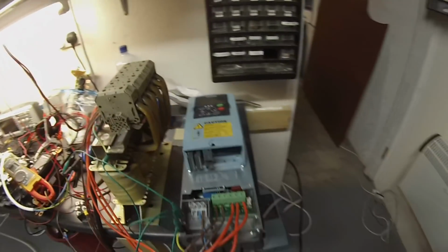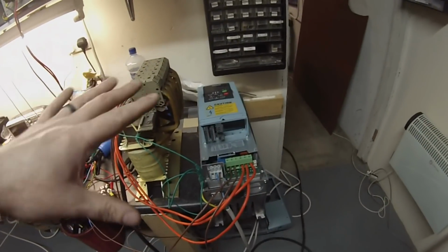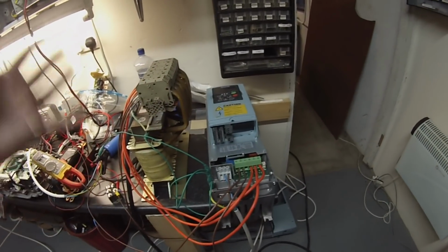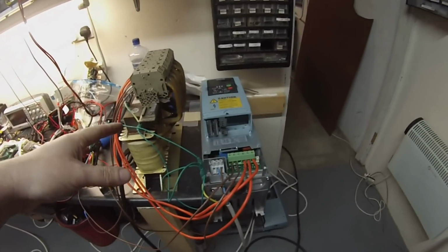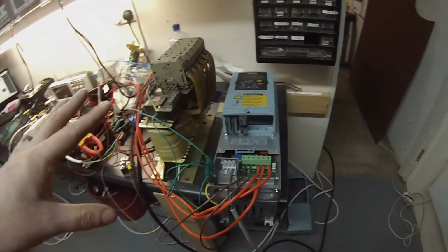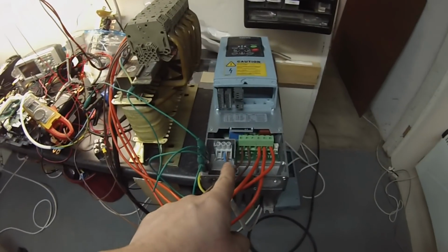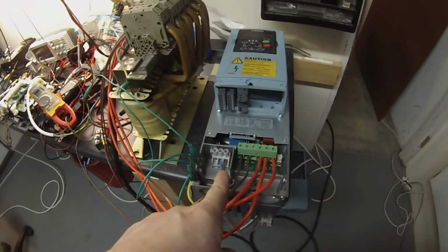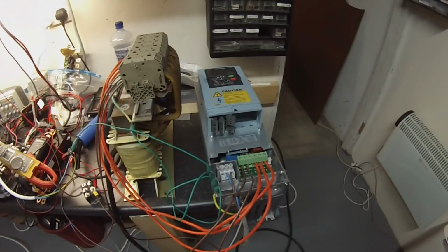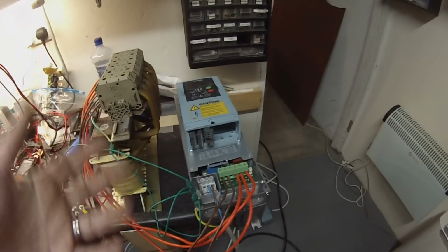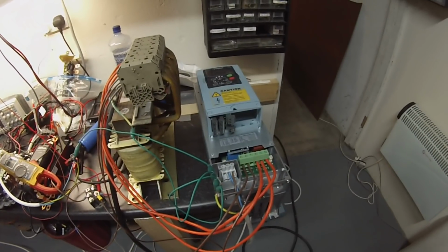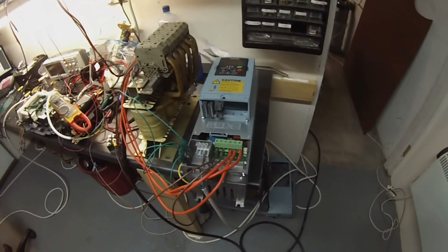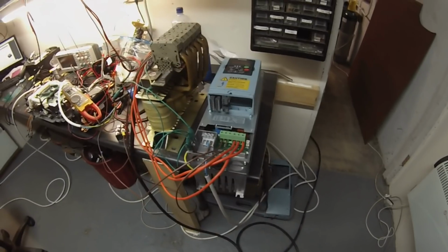So basically, what the Dino Guy showed was that you step up your 230 volt single phase to 400 volt single phase, feed that into your inverter, turn off the phase failure detection, set it to run 50 hertz, and you're all set. And that indeed did work.